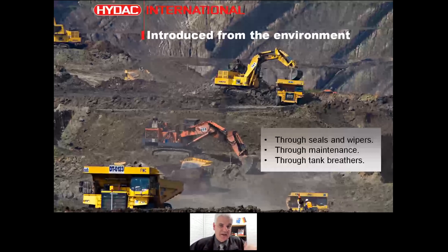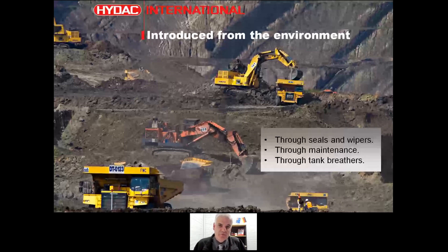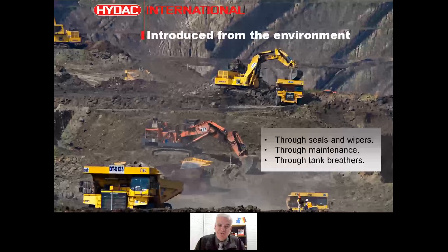Even the act of changing a filter element is an opportunity for contaminating your system. If you have a tank breather that's damaged, loose, off, or even lost, the environment gets in there. We think of air as being clean because we can see through it, but compared to the cleanliness we need in these systems, if the system is breathing normal industrial air, it's filthy. So contaminants are introduced during manufacture, during use, and from the environment.